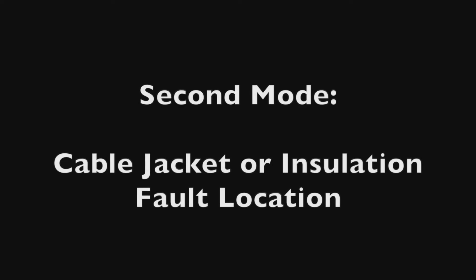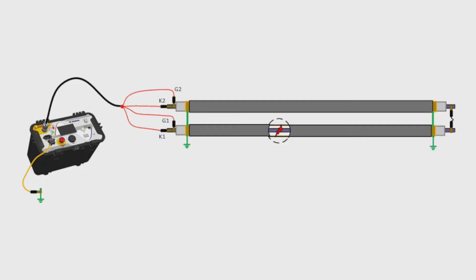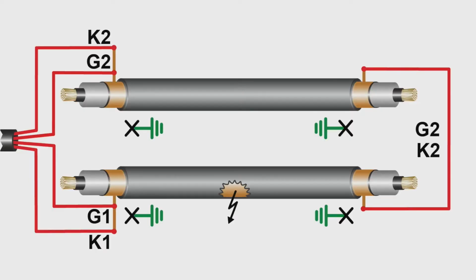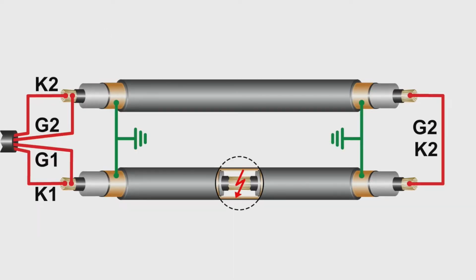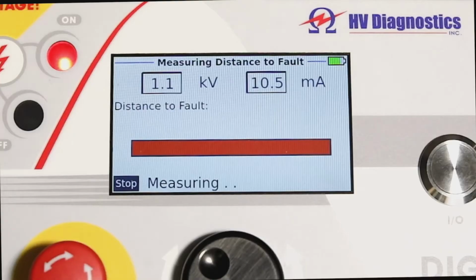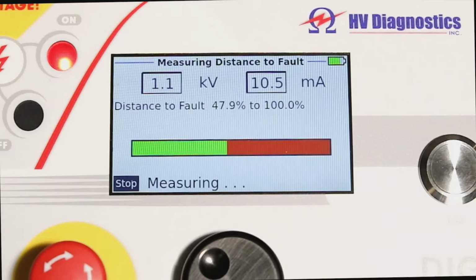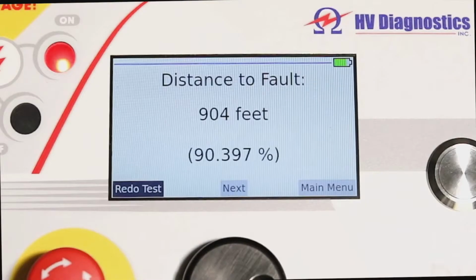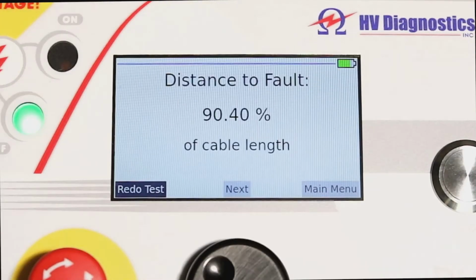The second mode is a fault pre-location mode, used if there's a fault detected in the cable. This is effective for both faults in the cable jacket from the first test or from the cable insulation. The fault pre-location mode will pre-locate the exact position of the fault, allowing the user to identify the zone or section where the fault is located quickly and accurately. The unit will show the position of the fault in meters, feet, or percentage of cable length.